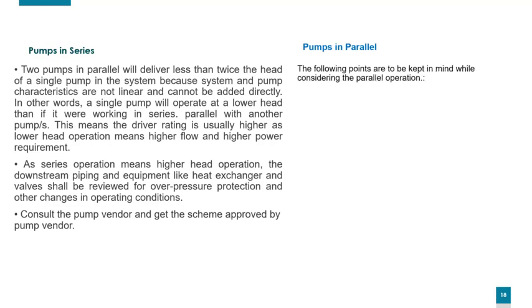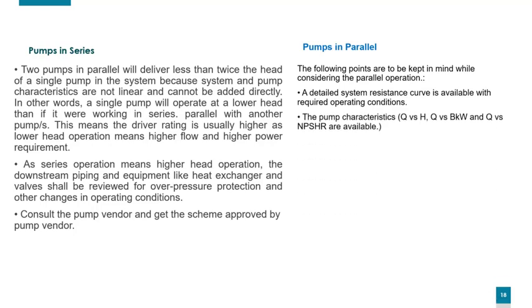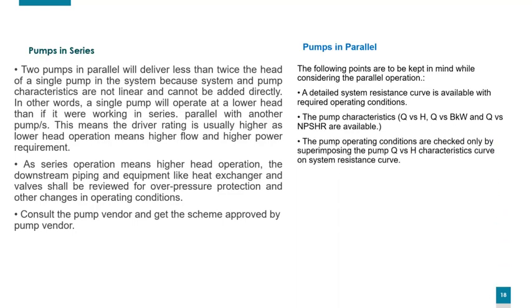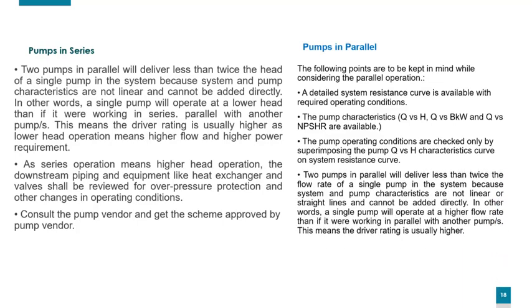While in the pump in parallel, the following points are to be kept in mind while considering the parallel operation. First, a detailed system resistance curve is available with required operation condition. Second, the pump characteristics are available, including NPSHR. The pump operating conditions are checked only by superimposing the pump Q versus H characteristic curve on system resistance curve. Two pumps in parallel will deliver less than twice the flow rate of a single pump in the system because system and pump characteristics are not linear or straight lines and cannot be added directly. In other words, a single pump will operate at a higher flow rate than if it were working in parallel with another pump. This means the driver rating is usually higher. Consult the pump vendor and get the scheme approved by pump vendor.